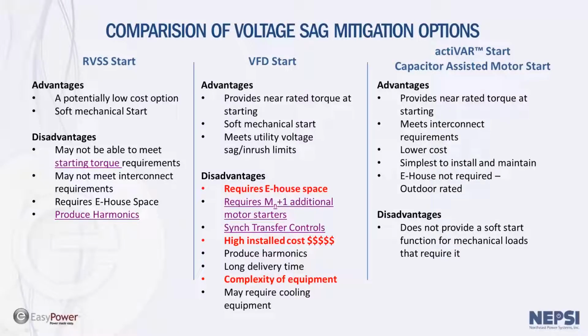The actiVAR, or the capacitor assisted motor start, comes in at a lower cost than the VFD starter, but at a much higher cost than the soft start. So it's definitely an option that should be considered. It can be sized such that the voltage sag to the motor is kept within the limits dictated by the local utility. And it can be sized to meet the local utility requirements for both inrush current and voltage sag limits.